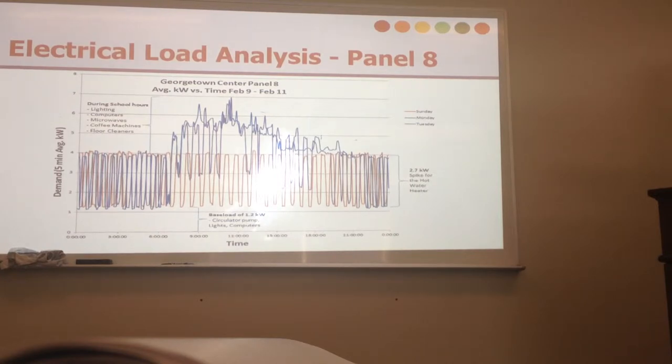Is there any refrigerators in the staff room? There is. I don't have that in the chart, but I was going to mention it. So that I think needs to be added to the 2.7 kilowatt spike, because you're seeing it on the weekends as well, and overnight, there's a consistent spike. There's some little blip here, kind of every once in a while it's a little bit higher, and there's a weird spike here, so it's not exact signs. That could be just down here too, this is always fluctuating, and it's not always going to be right at 1.2, it could be a bit more or less, and that would affect the whole spike.